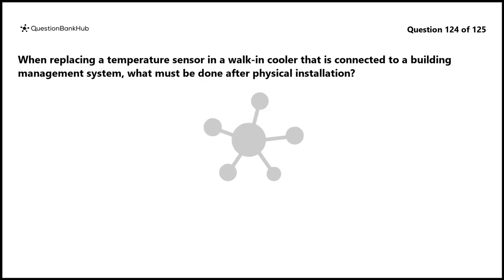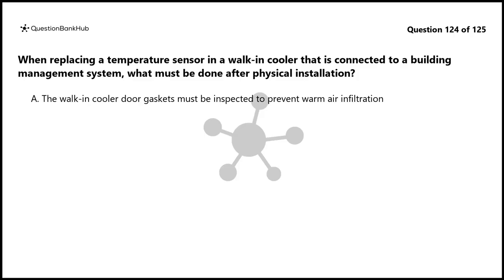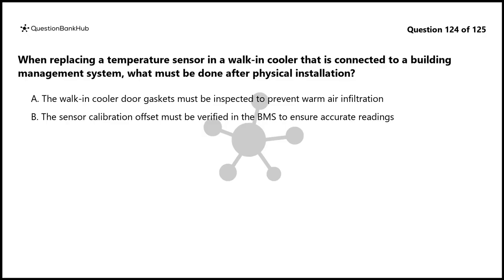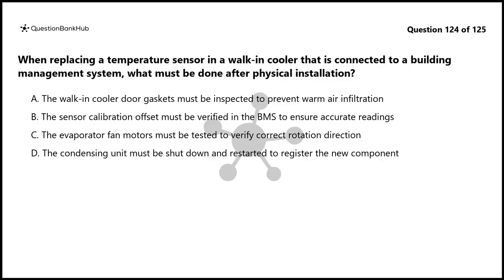Question 124. When replacing a temperature sensor in a walk-in cooler that is connected to a building management system, what must be done after physical installation? A. The walk-in cooler door gaskets must be inspected to prevent warm air infiltration. B. The sensor calibration offset must be verified in the BMS to ensure accurate readings. C. The evaporator fan motors must be tested to verify correct rotation direction. D. The condensing unit must be shut down and restarted to register the new component.